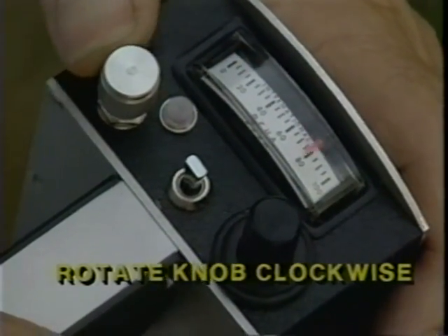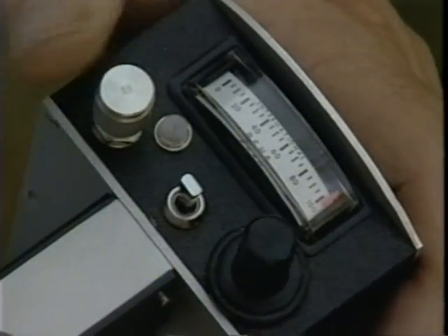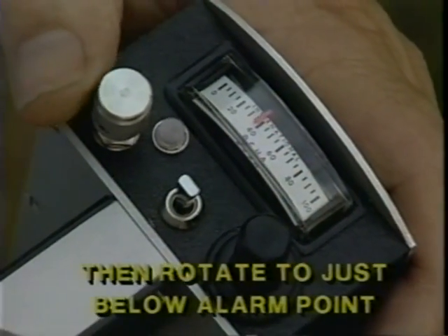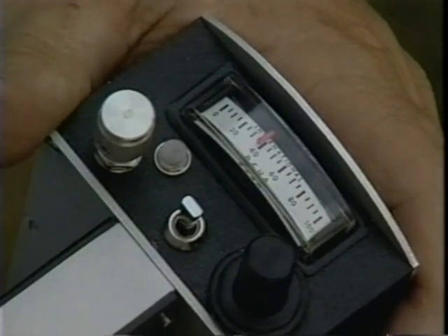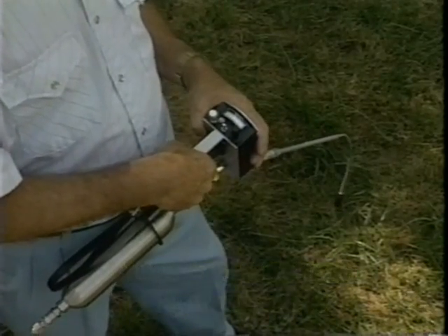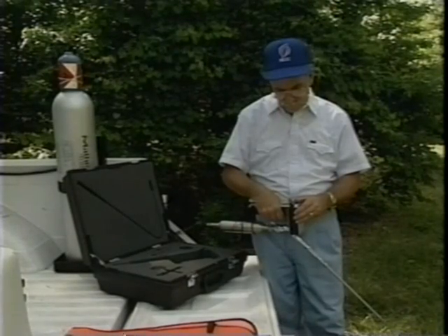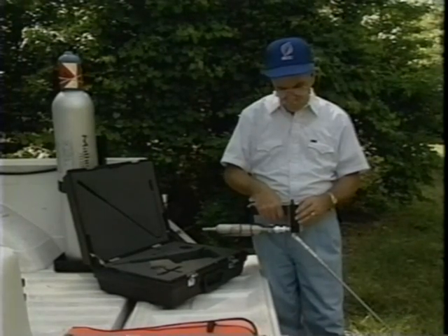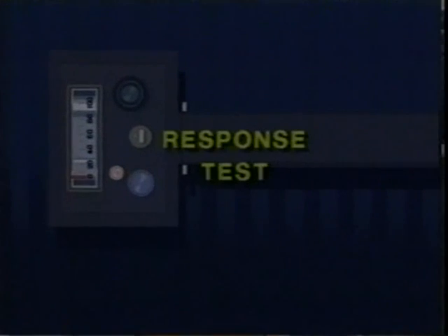Rotate the balance knob clockwise until the alarm sounds. Then rotate the knob counterclockwise to just below the alarm point. Allow the unit to warm up for 5 minutes before attempting a survey. This will allow the FlamePack 400's electronic components to fully stabilize. A response test is necessary on every startup and any time leaks are not found as expected.